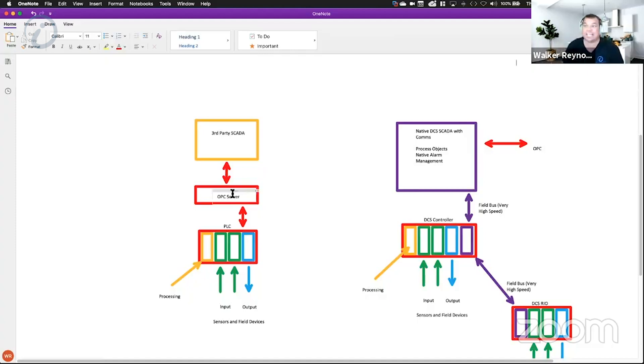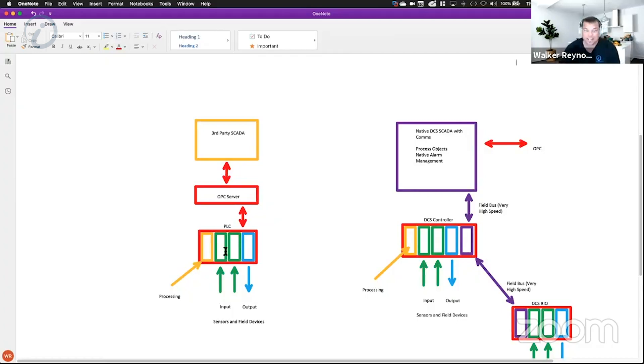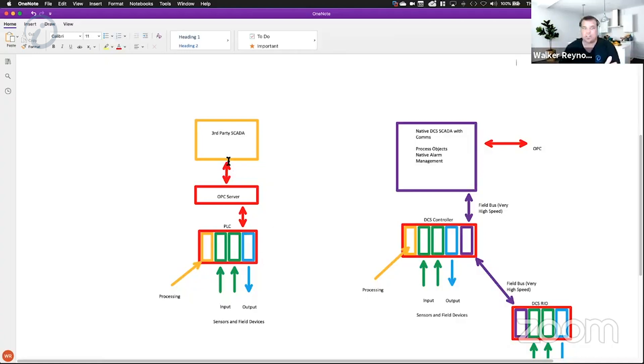When the OPC server gets installed, it is blank — there are no channels, devices, or tags configured. You have to engineer that. When the PLC gets installed, it is empty. You have to update the firmware, configure each of the individual IO cards, and then write your ladder logic, sequential function charts, or function blocks to do your automation. Think of all of this as off-the-shelf — it's like buying the wood, buying the nails, and then hammering everything together.